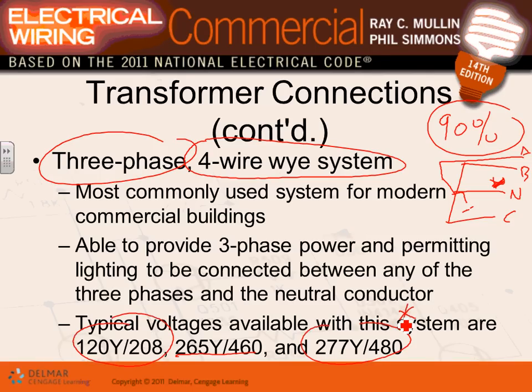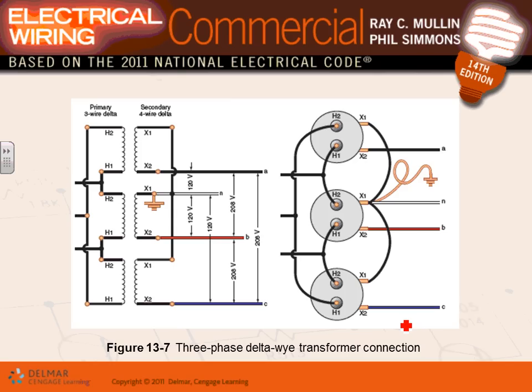That's considered low voltage. What's high voltage? Higher than 600 volts. So please pay attention to that one, if anything, nothing else. That's the most important. This is how we wire it. We looked at this diagram, guys, and we said this is not a delta. This is a Y.